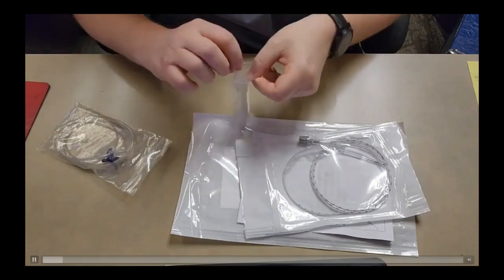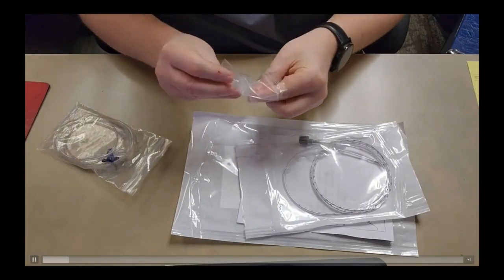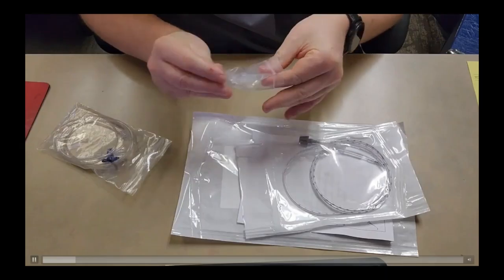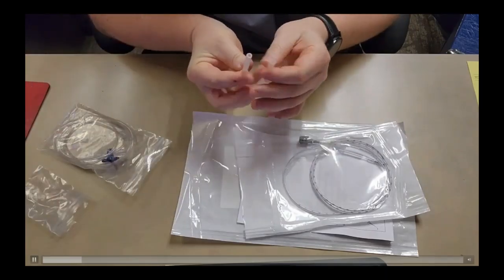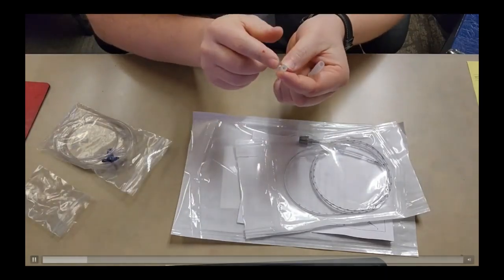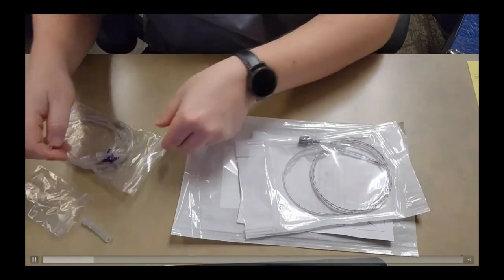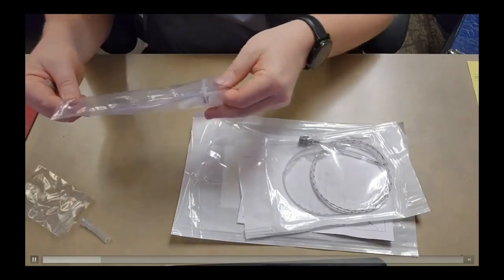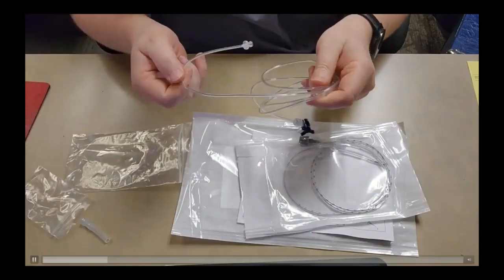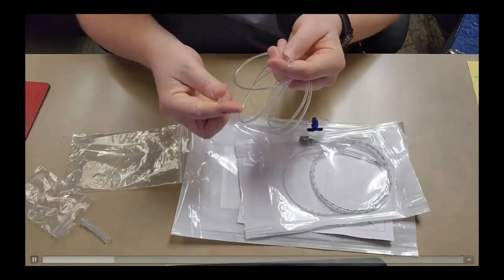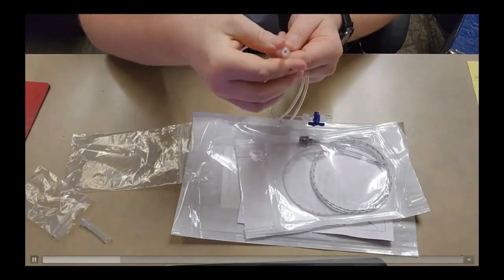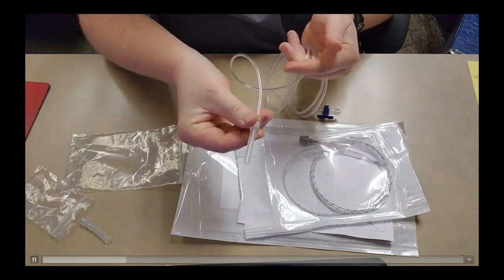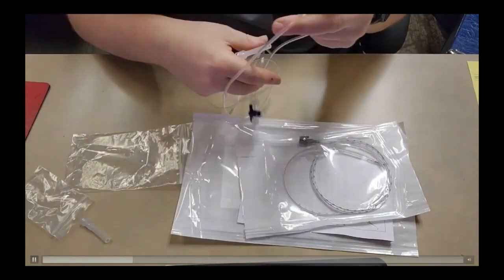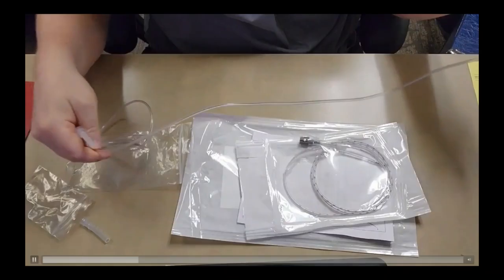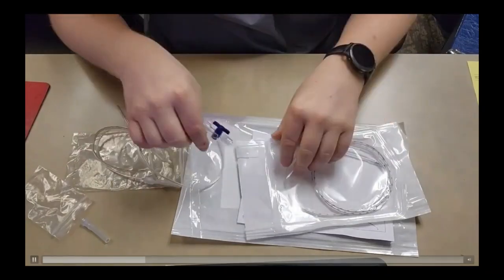Now, this particular esophageal balloon comes with two silicone plugs. You'll want to use the smaller one, which will attach to the end of the catheter. And then the opposite end of that silicone is going to attach to the light blue port on the ventilator. Next, you're going to take the opposite end and attach the stopcock to the balloon.